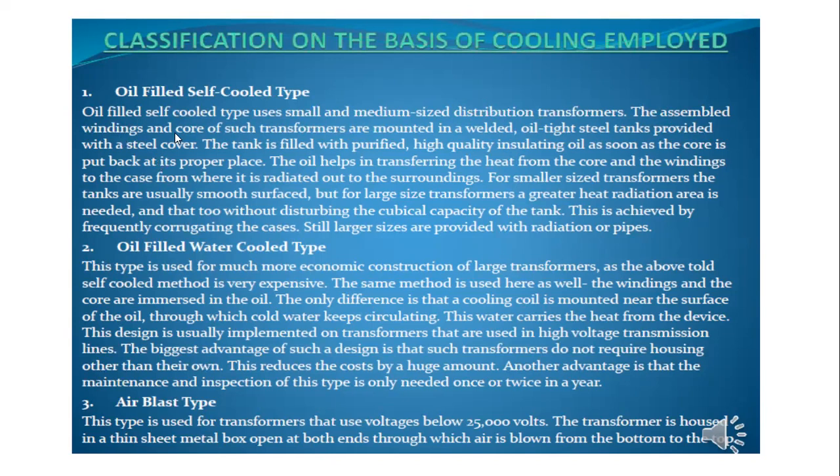The assembled windings and the core of such transformers are mounted in oil-tight steel tanks provided with a steel cover. In that we are using the tanks. The tank is filled with purified high quality insulating oil. This oil helps in transferring the heat from the core and the windings to the case, from where it is radiated. This is the oil-filled self-cooled transformer.